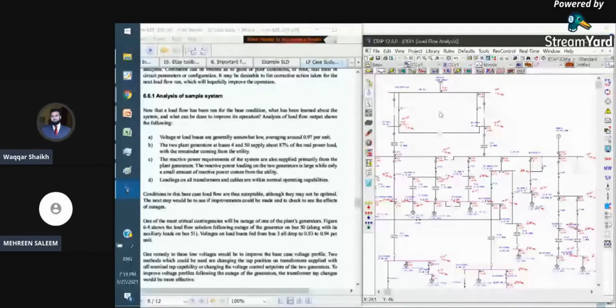You can see here, these are the results taken directly from the ETAP software for the sake of saving our time. So what he is saying, the two plant generators at bus 4 and 5 supply 87% of the real power load. So I can show here that these are 11,000 kilowatt, 8,000 kilowatt. If I add them together, here is the total active power contribution from the generators, and the active power contribution from the utility is 2906. Okay, so when I sum up all of them, the total active power contribution into the network will be 21906. Okay, this is the sum of all the three active powers.